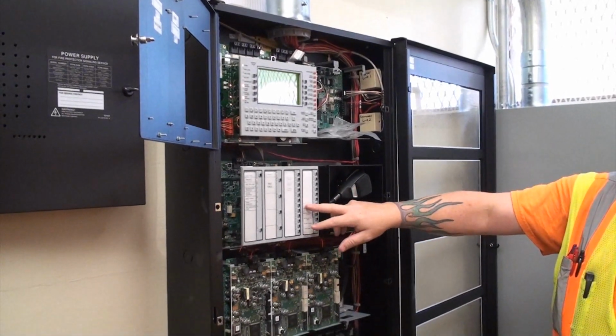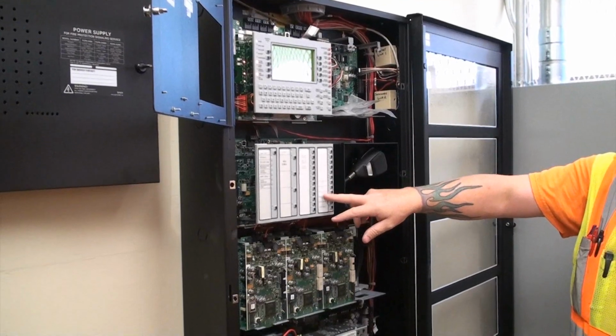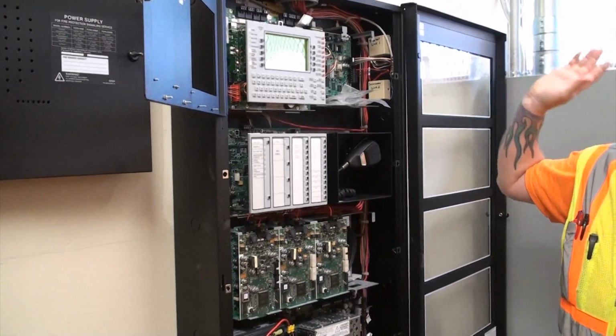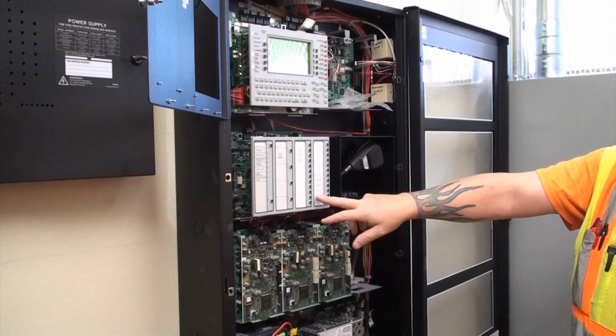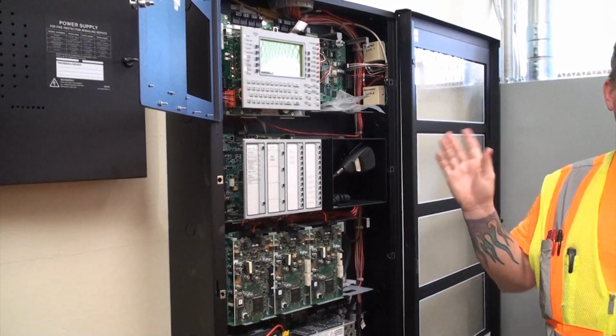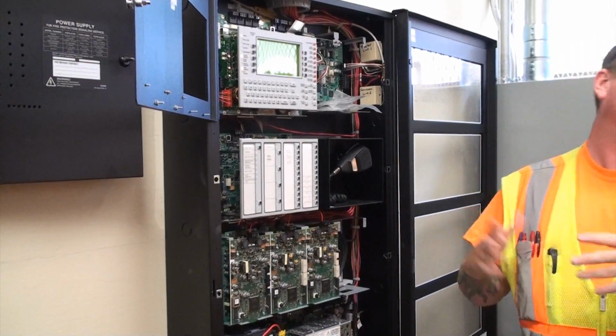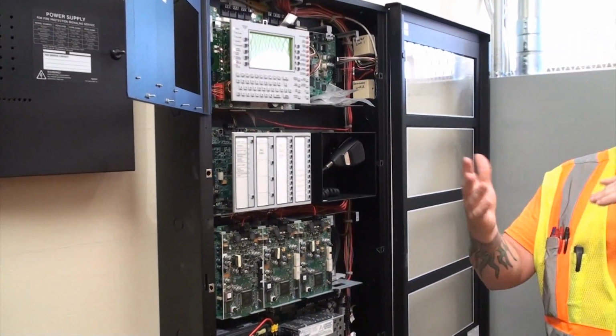So this one, I already have it pre-programmed for bypasses for the HVAC damper shutdown. So if you're working in the building, you can bypass those. You have a speaker bypass, a strobe bypass. So if you wanted to set off something and see the strobes flash but don't want to hear the speakers, you can do that, or vice versa with the strobes and the speakers.